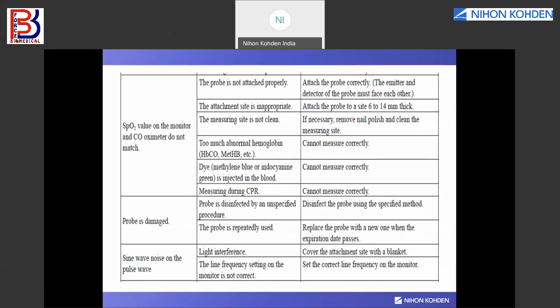There could be light interference. As you know, there is a red light and infrared light inside the SpO2 sensor, and its wavelength could match with the ambient light, the sunlight or the room light inside the ICU. It could interfere. So in that case, cover the site with a blanket or a black sheet so that the external light cannot interfere with the SpO2, both infrared and red light. There could also be a possibility that the frequency setting in the monitor may be incorrect. So change the frequency setting in the monitor.